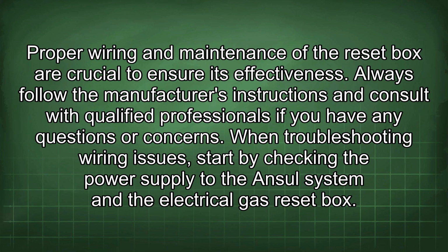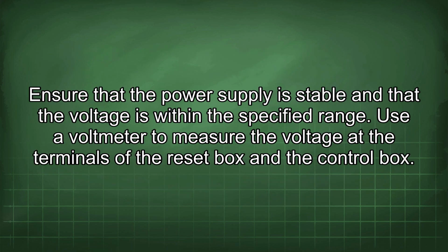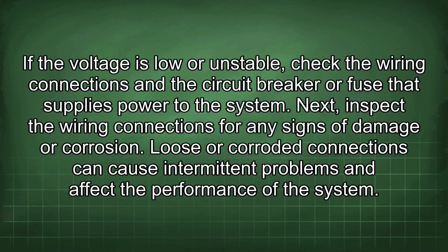When troubleshooting wiring issues, start by checking the power supply to the Ansul system and the electrical gas reset box. Ensure that the power supply is stable and that the voltage is within the specified range. Use a voltmeter to measure the voltage at the terminals of the reset box and the control box. If the voltage is low or unstable, check the wiring connections and the circuit breaker or fuse that supplies power to the system.